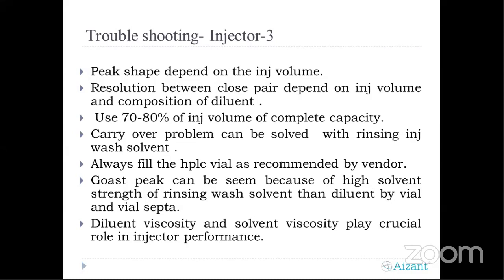Now, coming to the injection again, we think the injection has a problem, but it's very surprising that for HPLC vials provided by the vendor, there is a recommendation on how much you have to fill. If you fill the HPLC vial completely and keep on injecting, there is a pressure buildup because of the completely filled vial, and it will result in injector abnormalities. So we have to take care of that. The other point is the vial septa. If the diluent polarity we are using for sample preparation is different from the mobile phase, it can extract some leachables from your vial septa. So we have to be very vigilant about what septa we are using and how compatible they are with our diluent system or the mobile phase. If that is identified, I think we can resolve the ghost peak appearance.